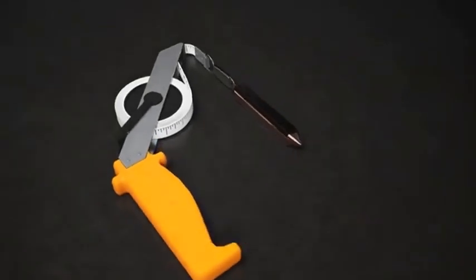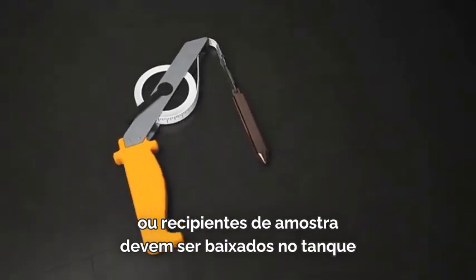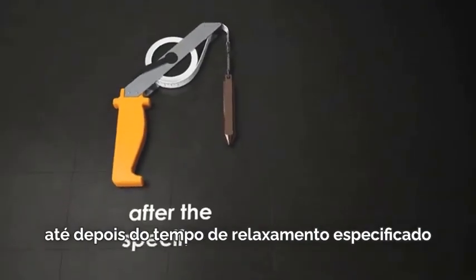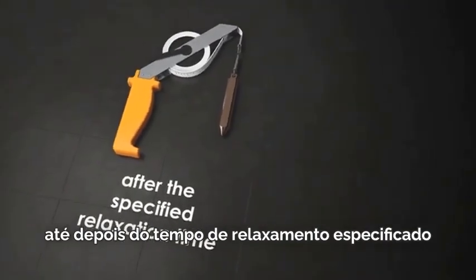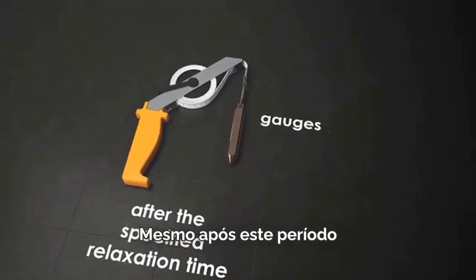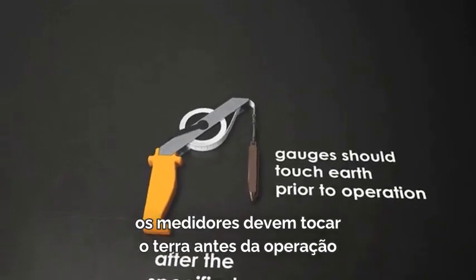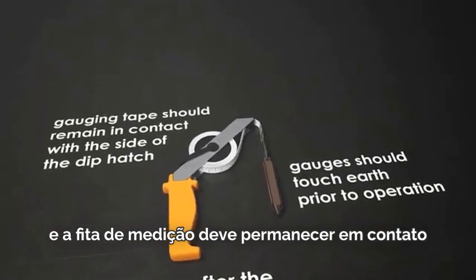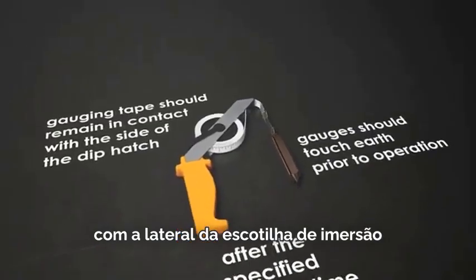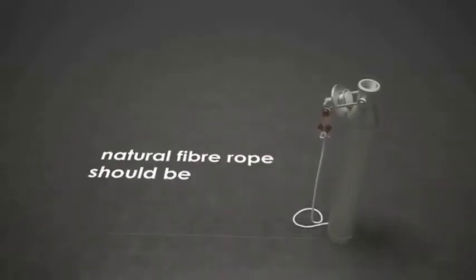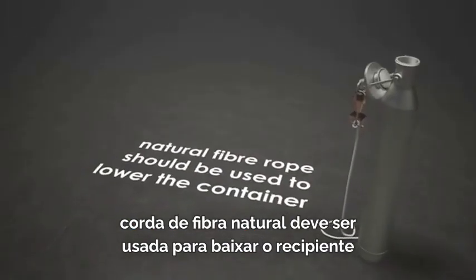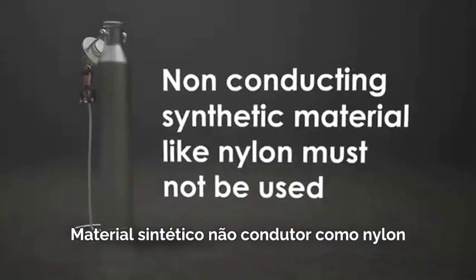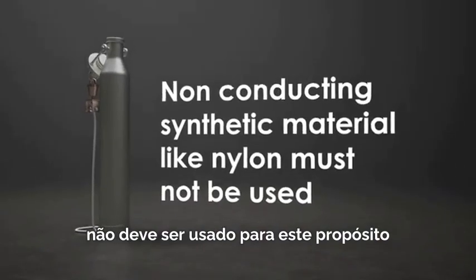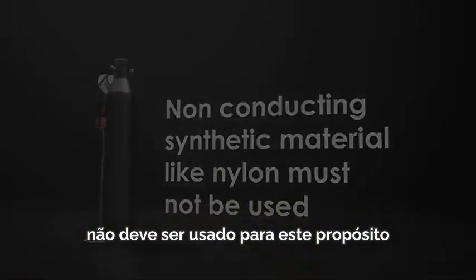No conducting objects such as gauge tapes or sample containers should be lowered into the tank until after the specified relaxation time. Even after this period, the gauges should touch earth prior to operation, and the gauging tape should remain in contact with the side of the dip hatch. When taking samples, natural fiber rope should be used to lower the container. Non-conducting synthetic material like nylon must not be used for this purpose.